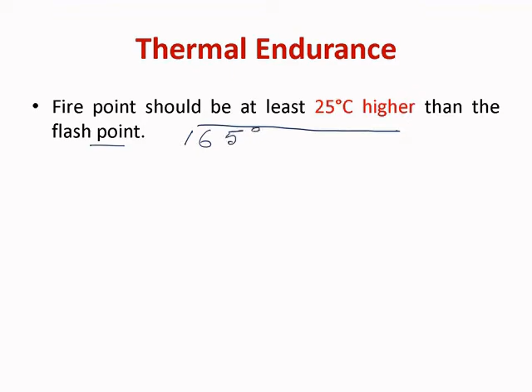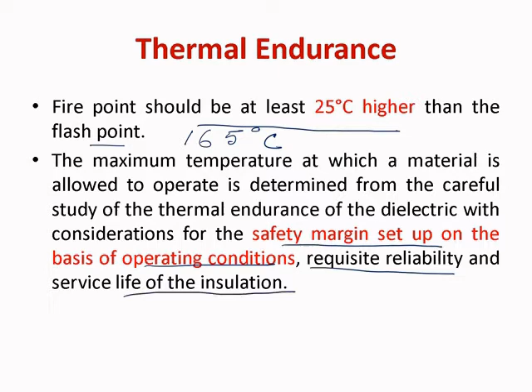The maximum temperature at which a material is allowed to operate is determined from a careful study of thermal endurance of the dielectric, with consideration for a safety margin set up on the basis of operating conditions, requisite reliability, and service life of the insulation. Generally, insulating materials operate satisfactorily within a temperature range. The upper limit of this temperature range is known as thermal endurance, and the lower limit of this temperature range is known as cold endurance.